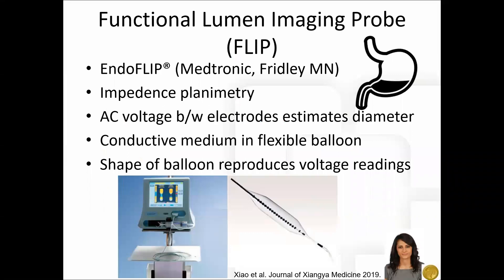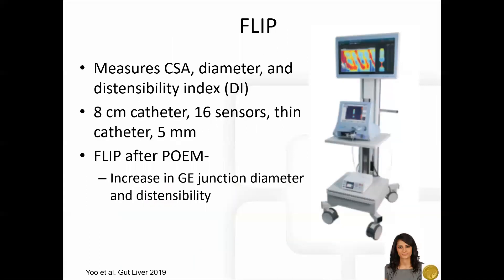Functional lumen imaging probe technology uses impedance planimetry to characterize the geometry of cross-sectional areas. A flexible balloon containing a conductive medium is used. It uses AC voltage measurements made between pairs of electrodes to create a topographic image that reflects the shape of the balloon and measures the cross-sectional area, diameter, and distensibility index. The catheter contains 16 electrodes spaced five millimeters apart in an eight centimeter balloon.